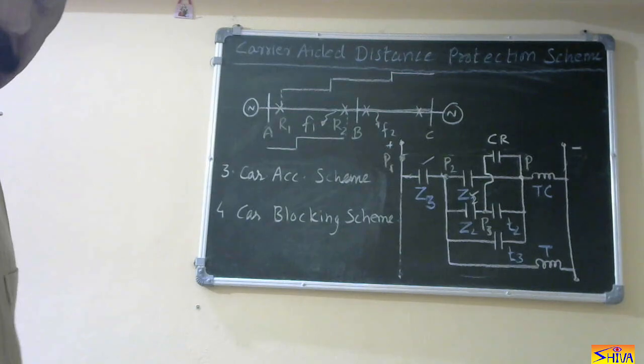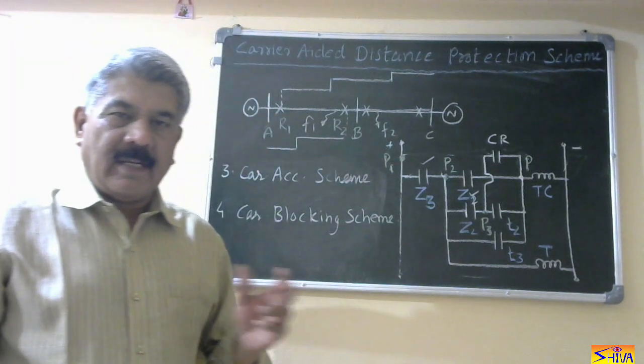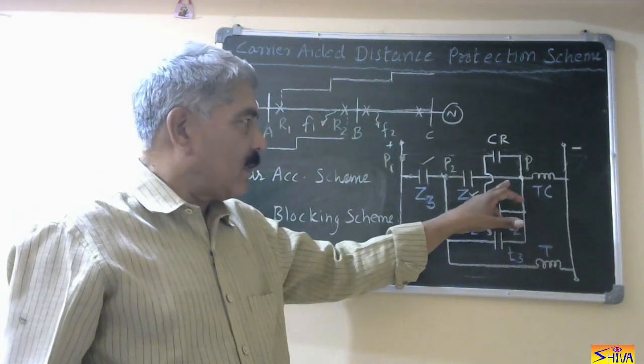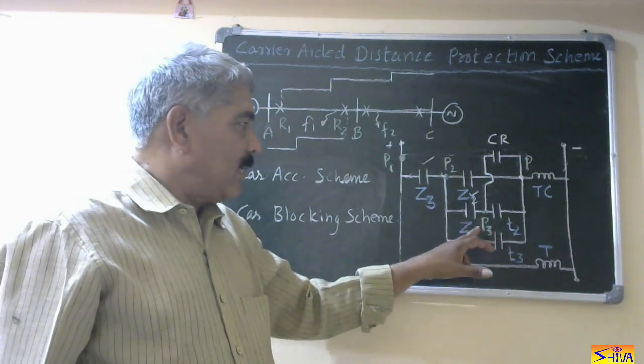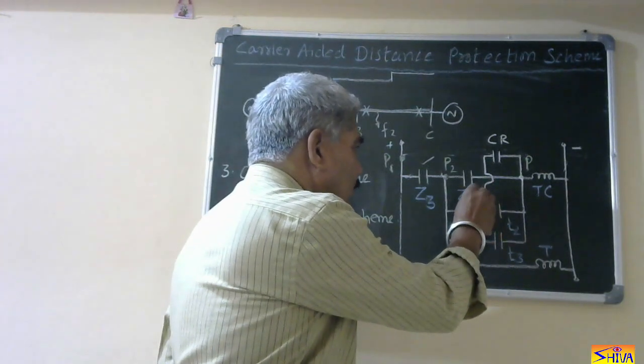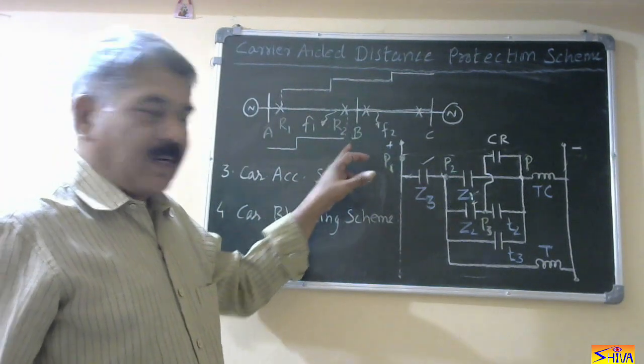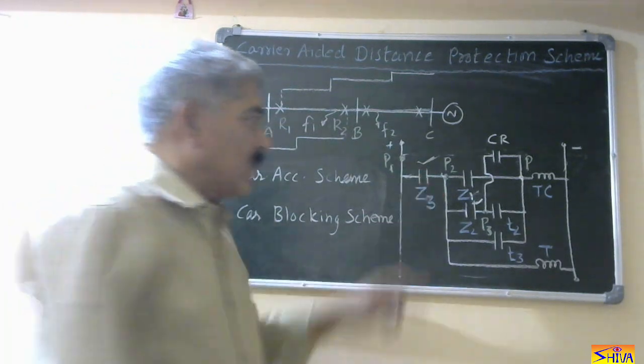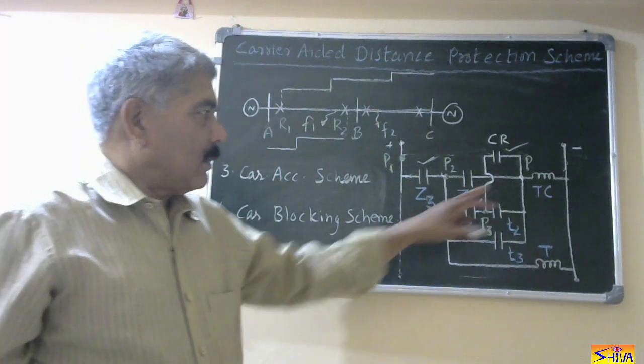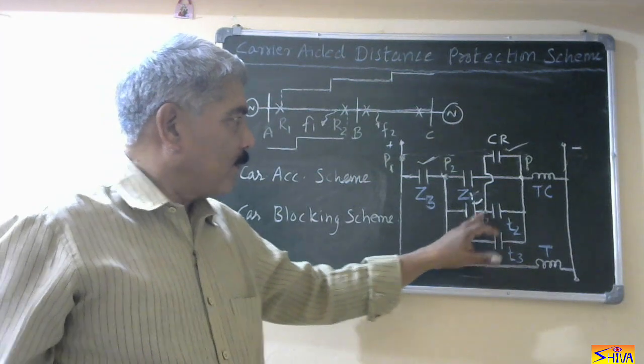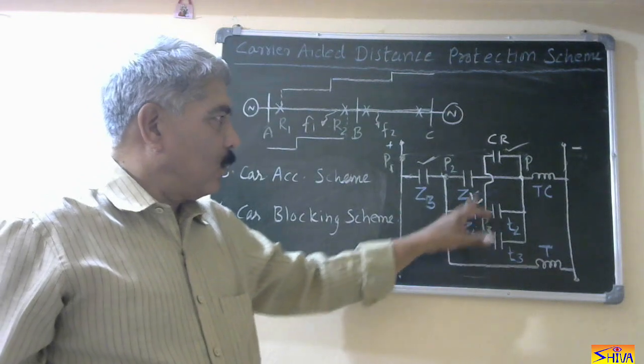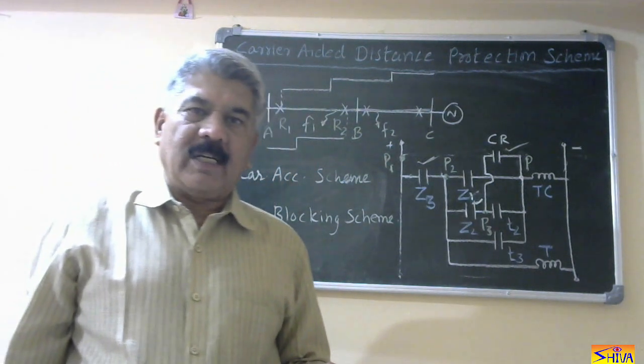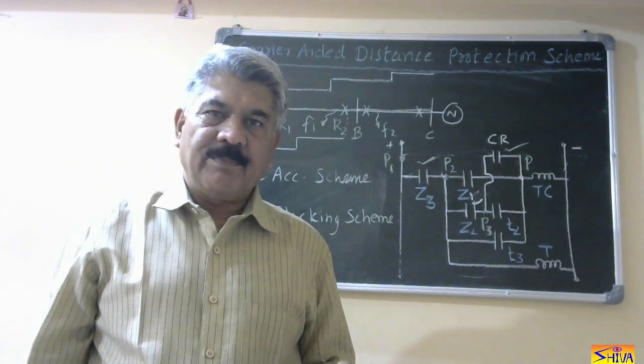Now let us see the third scheme — carrier acceleration scheme. In this scheme, the position of the carrier receive relay contact is changed from P2 to P3 — that is, after the Z2 contact. When fault F1 occurs, Z3 will close, Z2 will close, carrier signals are transmitted, and as soon as the carrier receive relay receives the signal it closes its contact. The trip coil is energized through Z3, Z2, and CR. Advantages are the same: circuit breakers at both ends operate simultaneously, fast fault clearing, and improved transient stability.